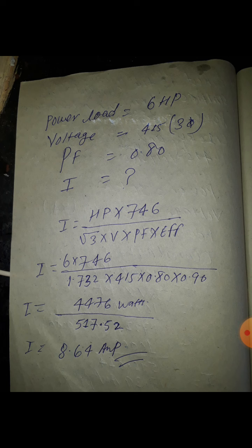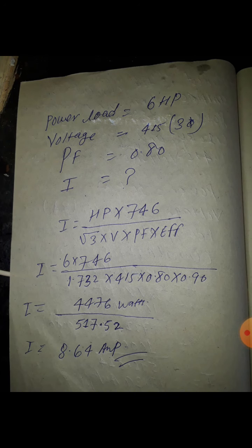So after calculating, the total load is 8.64 amps. We don't have an 8.64 amp MCB, so we can use a 10 amp MCB, a little bit higher.